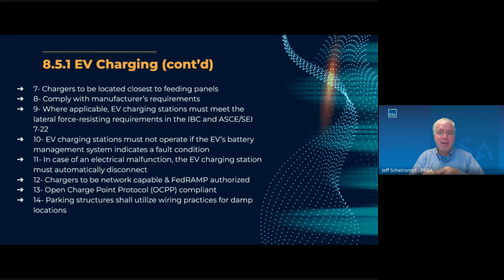So first off, we have limited ampacity before we have to perform significant electrical upgrades. We may need to limit when the vehicles charge. We may have to limit how many can actually charge at once, or what power levels we can actually allow them to charge at. And then next up, we need to limit our exposure to peak demand charges. If you're not familiar with peak demand, that's a line item on our electric bills that is based upon the highest period of usage, usually 15-minute intervals, over the billing period. So if we're not careful with how we allow vehicles to charge, we will, no doubt in my mind, end up paying more for that peak demand item than we actually pay for the actual power used. So if we get sloppy with the controls, our monthly bills are going to be a lot more than they need to be.